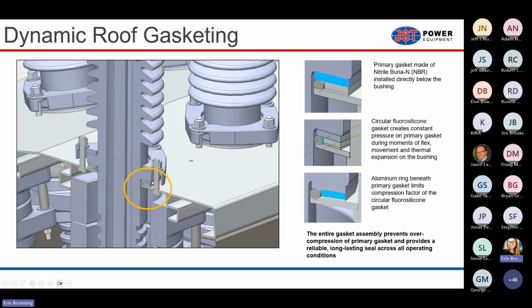Additionally, the gasketing system of the roof bushings is a three gasket system where you have the primary gasket that sits underneath the bushing. That's the top one here. And then you have a circular gasket underneath. And then you have an outer aluminum ring. But it basically forces the circular gasket to maintain its rigidity.